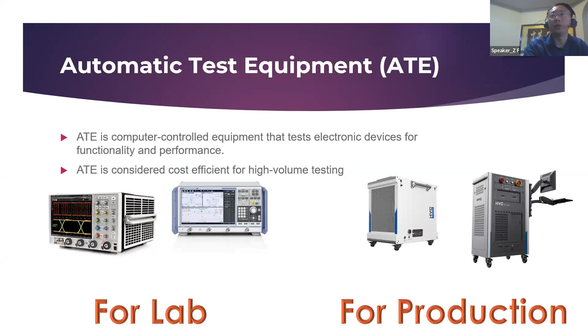ATE consists of many components, from the actual instrument to the handler, a socket, and DUT board, load board. The tester is the heart of the system that includes the control hardware, sensor, and software, which collects and analyzes the test result. The tester is the instrument, or multiple instruments together, performing a functional test or performance test on your product. During the test, a preset of patterns is sent to your DUT, and then the output is analyzed against a set of limits. The result is then passed to the handler.